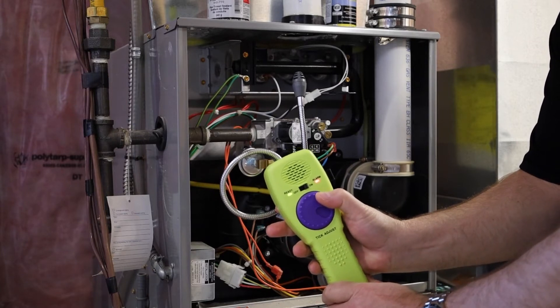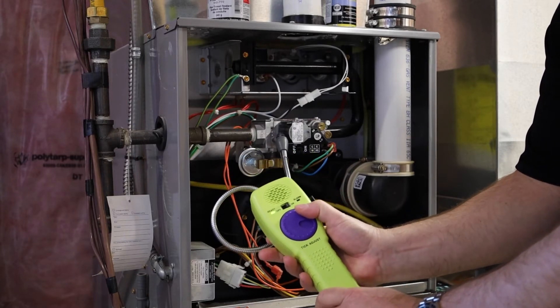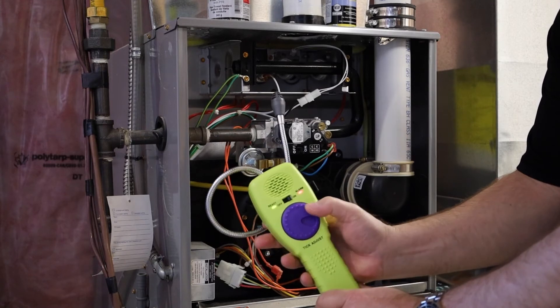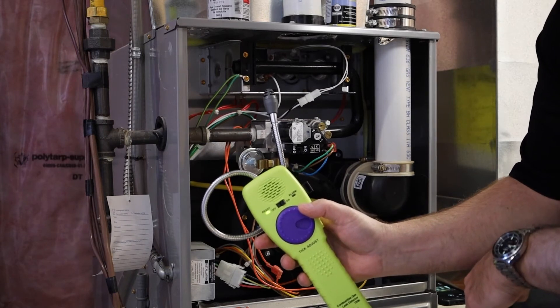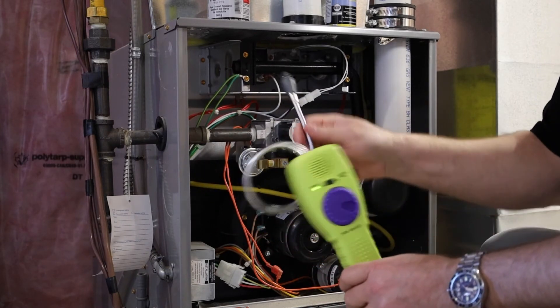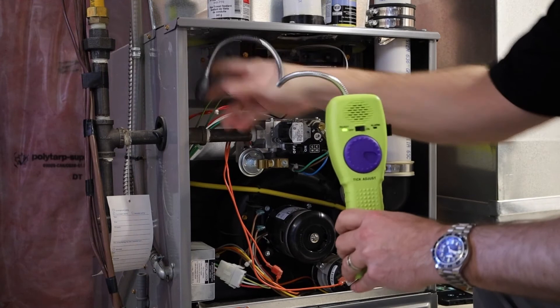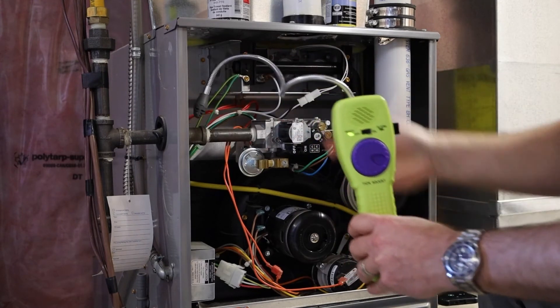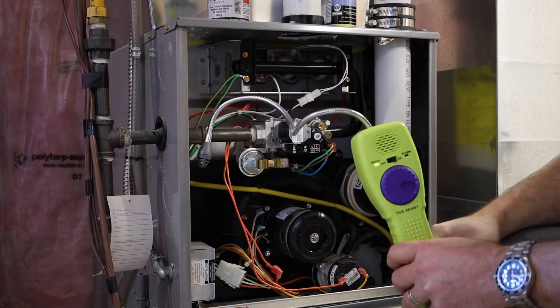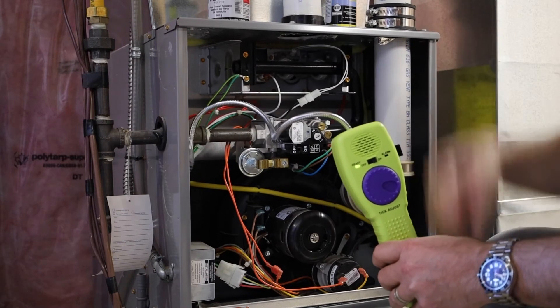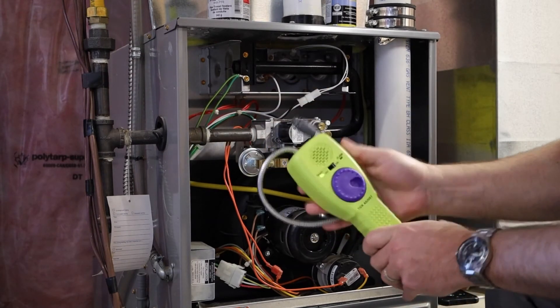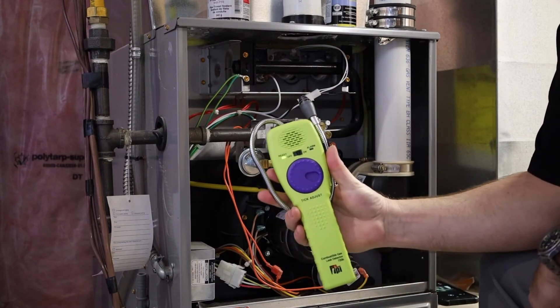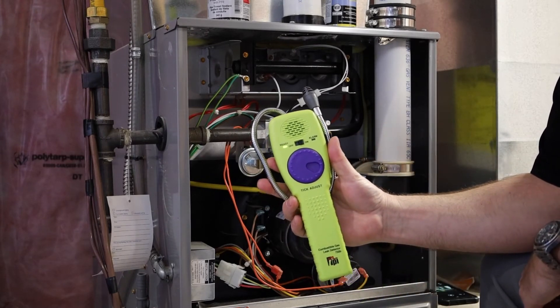Tune it out. And again, higher ppm, it's going to check again. And of course the highest ppm is going to be the source of your leak. Again, flexible gooseneck. Hard to reach spots behind this coupling or it could be a union that's a very common place for a leak. Or it could be a shutoff valve. There's the TPI 720B.